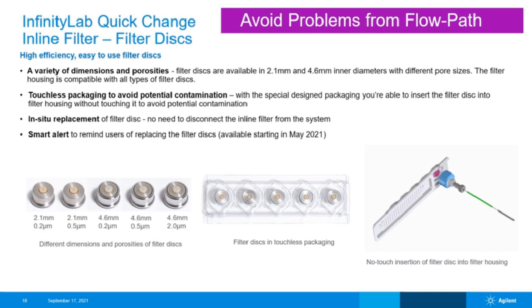As just shown in the short video, we designed a unique touchless packaging to enable a no-touch insertion of filter disc into filter housing to avoid potential contamination. Besides, the filter disc can be replaced without disconnecting the inline filter from the system.